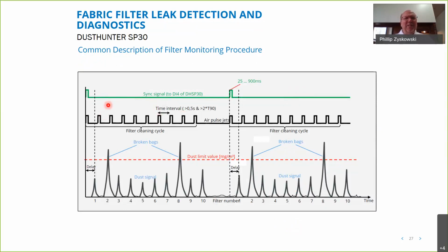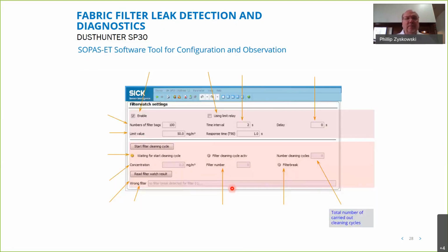So the key is to synchronize the SP30 to your baghouse cleaning cycles. And so you can see here, here's the signal coming into our Dust Hunter. And you can see these time intervals, the sawtooth here, and what happens when broken bags occur. And these are specifically filter numbers. So there is a delay here, and we can build in that delay as well. And I'll show you in a second how that's done.